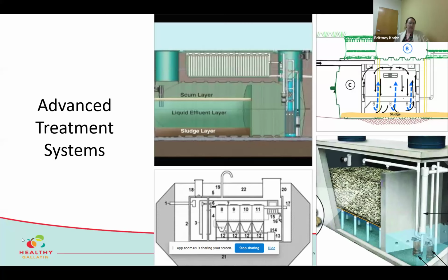What is an advanced treatment system? Well, if you can think about a motorcycle sidecar, maybe as a good analogy to the septic tank. We have things like the top one here, which is a tightly folded filter fabric, where it takes the effluent through a dosing system, sprays it over this media with an active air intake. So you're getting that aerobic change, and then it sends it back to the tank to complete the conversion of ammonia to really N2 is what you're trying to get to, to off-gas that nitrogen rather than nitrate into the groundwater.